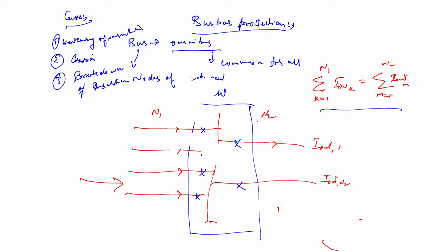Now, the probability of a busbar fault is very low. Because of that low probability, for many years it was considered unnecessary to provide explicit protection to the busbar. It was felt at that time that maloperation of the busbar protection system would be problematic by itself and of little help in sensing genuine faults.